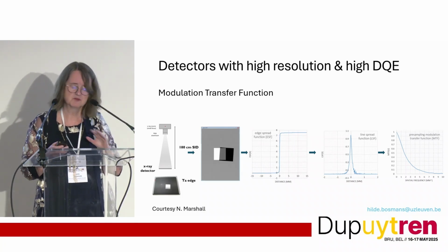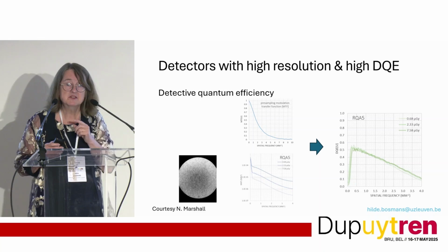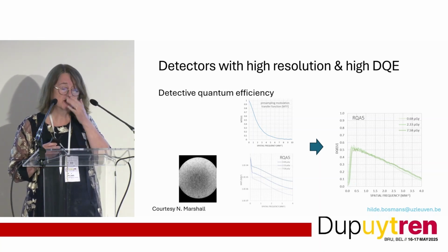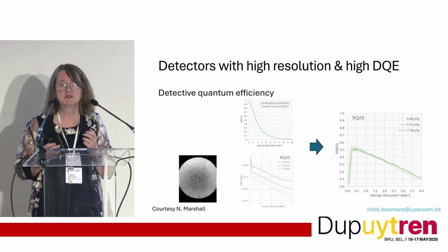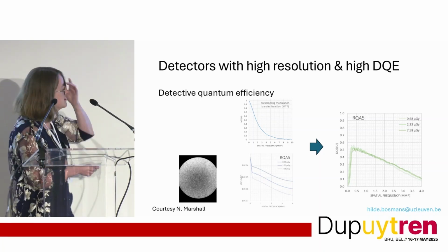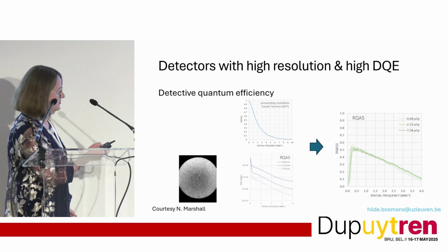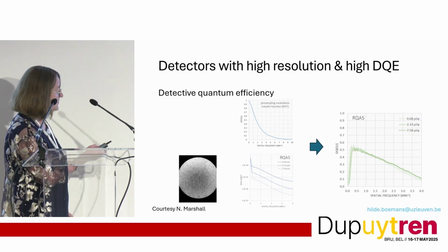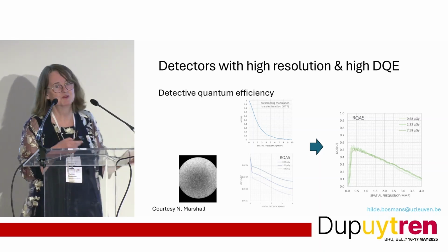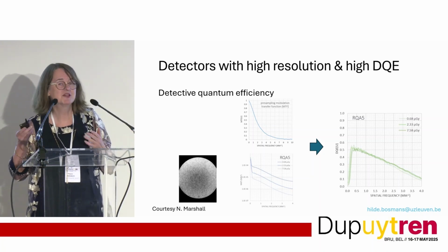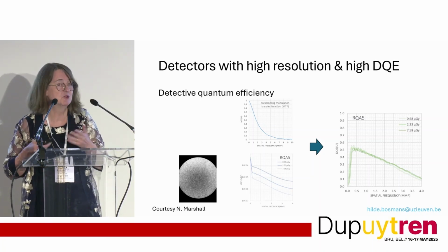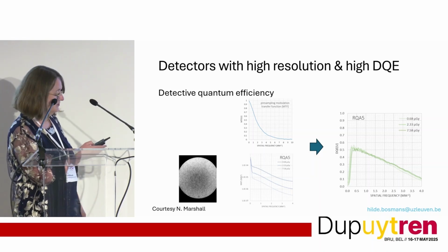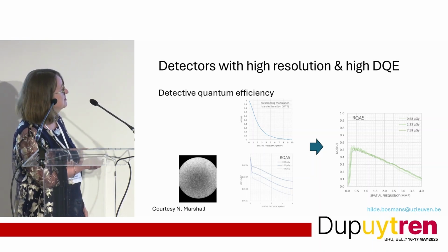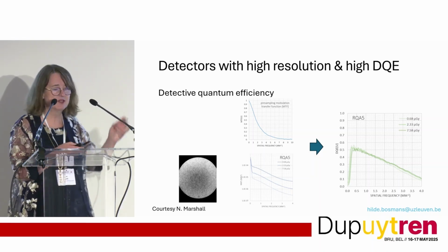But anyway, higher. Next to this, we want the detector to absorb everything, not to lose data. And we combine this in what we call the DQE. If you want to remember one other magic thing, DQE. Higher DQE means better detector. And the DQE curve is something like this. The higher, really the higher, the better.